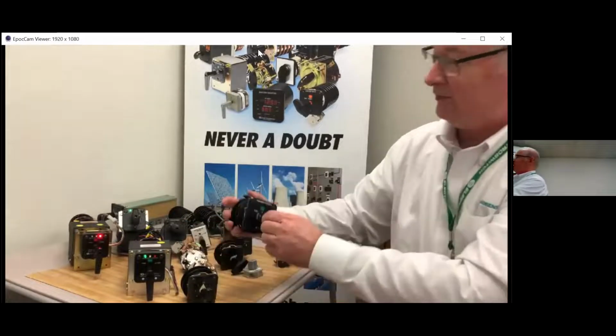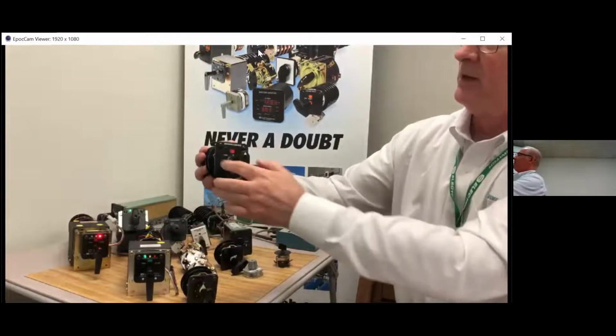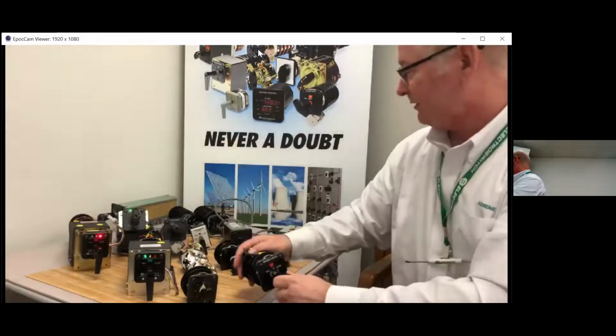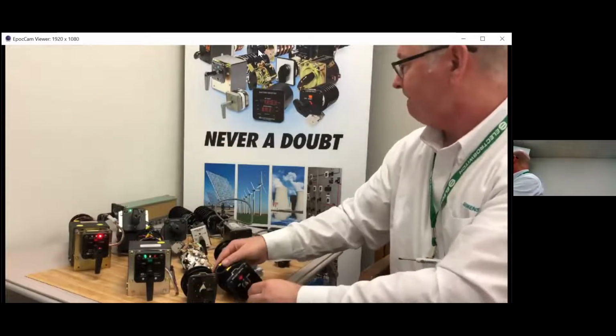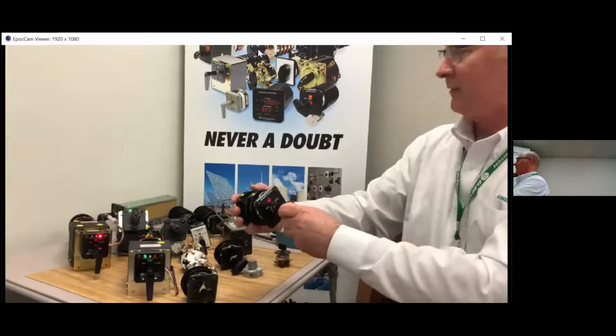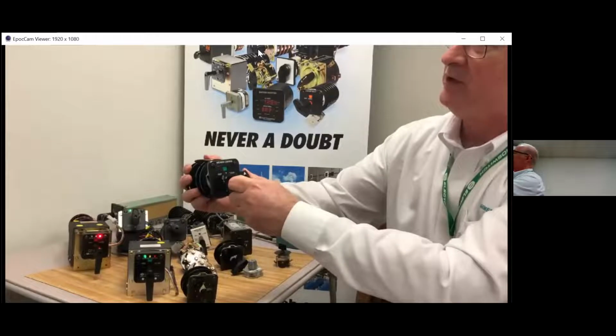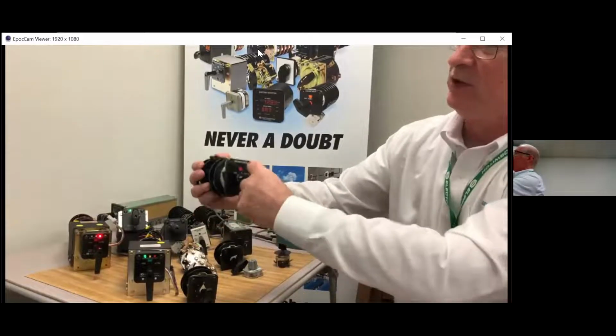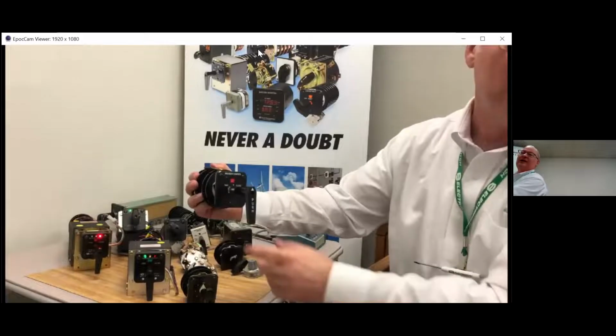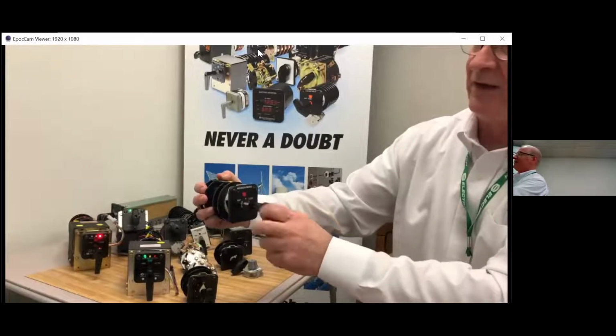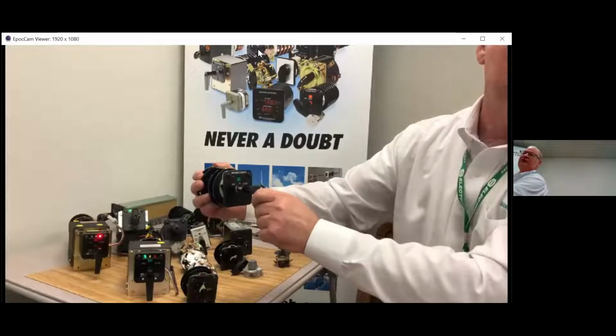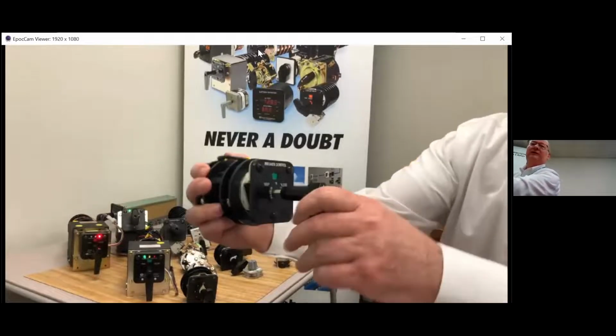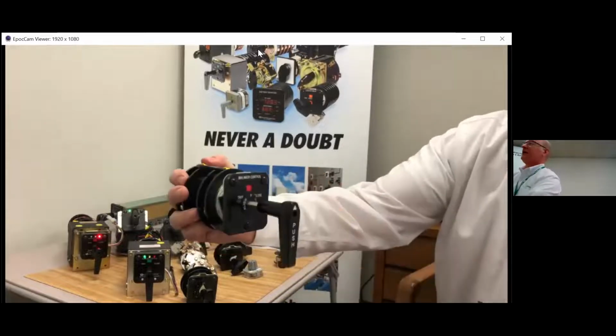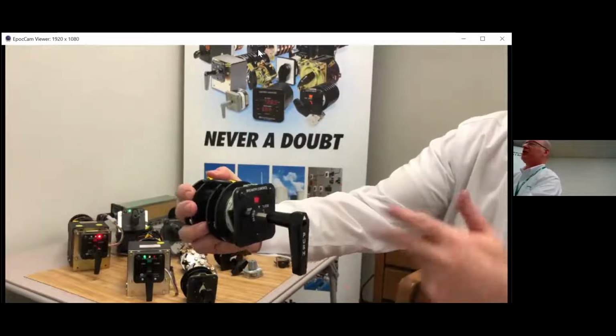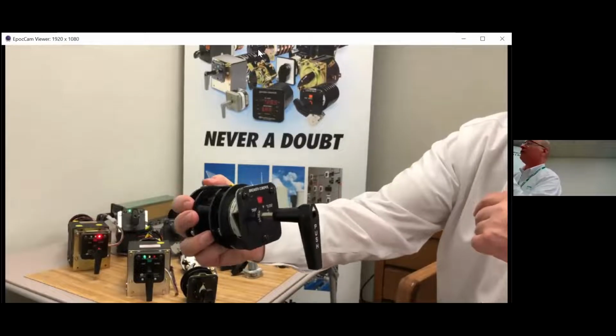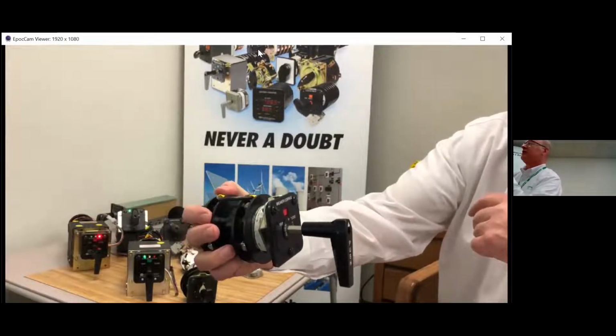But I also have what is called a spring return. In this case, I'll move it in a trip position and then it springs back to center. I move it to the closed position and it springs back to center. This particular switch has a bump-proof handle on it, so it does spring return on. Hopefully you can hear that operation. And it springs back to the center position. So those are common applications for a breaker control switch in an electric utility substation.